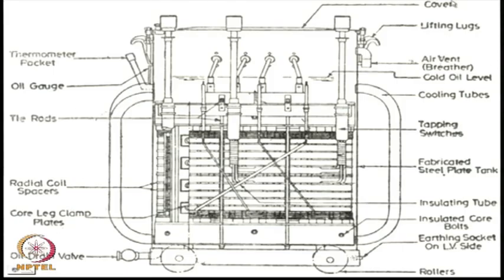So, this is the breather, this is the cold oil level here, it is above the transformer, these are the cooling tubes, this is again the tapping switches here, this is the steel tank, these are the core clamps, these are the insulated bolts, and this is the earthing socket. See, the transformer oil needs to be periodically changed. So, there is an oil drain valve, these are the coils, you can place an oil gauge here, and there is a provision for inserting a thermometer, so that you can measure the temperature rise of the oil from outside.